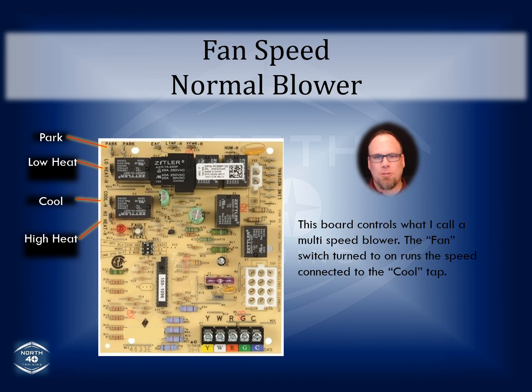Your fan speeds, traditionally, as we were just looking at on the manufacturer's guidelines that I just had pulled up a minute ago, you had 4 fan speeds. You had the high, you had the medium, then you had medium low, and then you had low. Okay, so if you look at this board, you've got a spot for your high heat, your cool, your low heat, and then there's 2 up in the top left-hand corner. They're called park. Park is not energized. It's a place for you to put any spare fan speeds that you don't want energized, and it's in lieu of the way we used to do things. The way we used to do things was to just tape it up and leave it hang, or strap it to another bundle of wires. Now you just run that to the board, and that's an unenergized terminal.